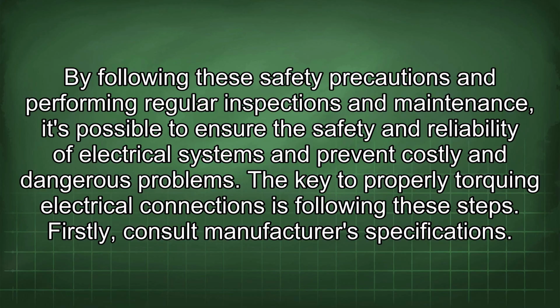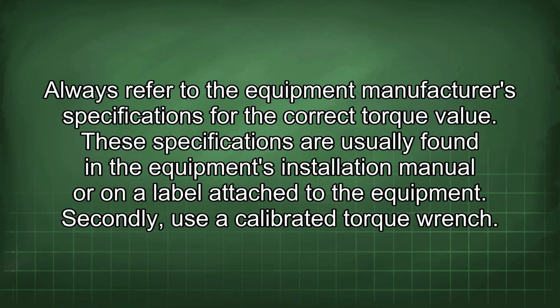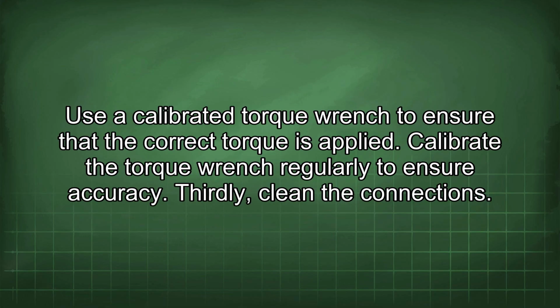The key to properly torquing electrical connections is following these steps. Firstly, consult manufacturer's specifications. Always refer to the equipment manufacturer's specifications for the correct torque value. These specifications are usually found in the equipment's installation manual or on a label attached to the equipment. Secondly, use a calibrated torque wrench. Use a calibrated torque wrench to ensure that the correct torque is applied. Calibrate the torque wrench regularly to ensure accuracy.